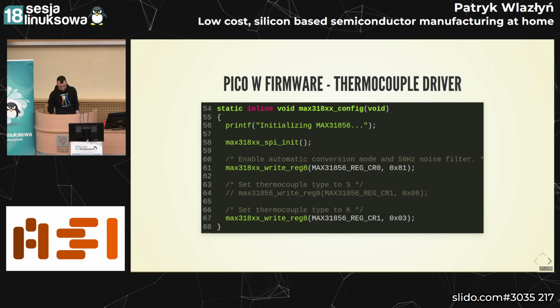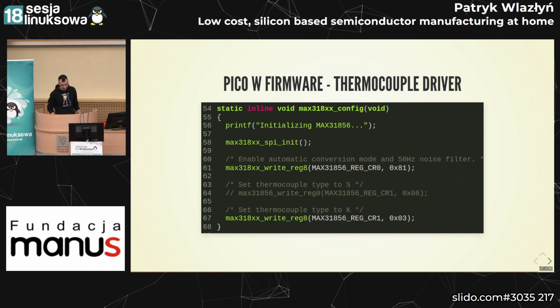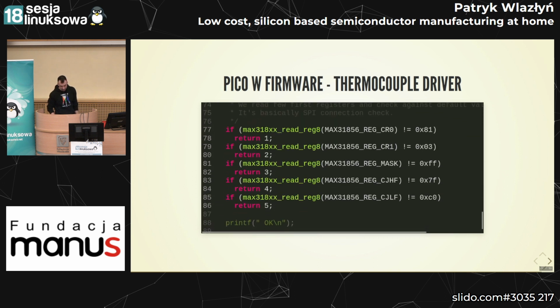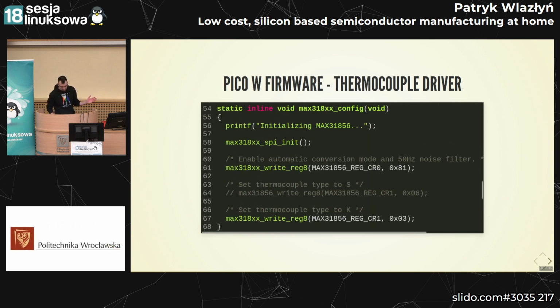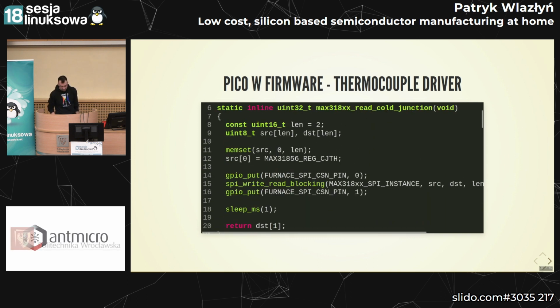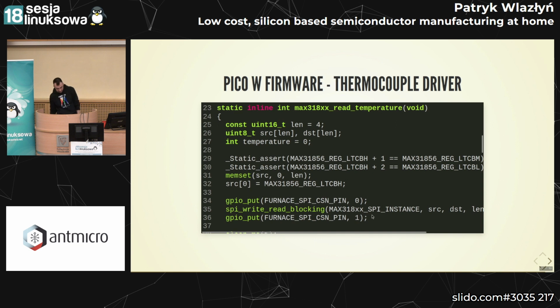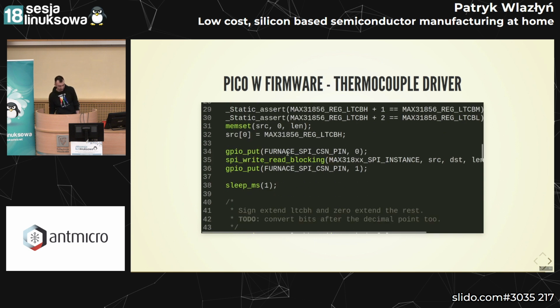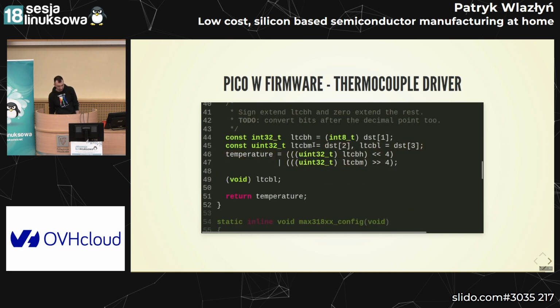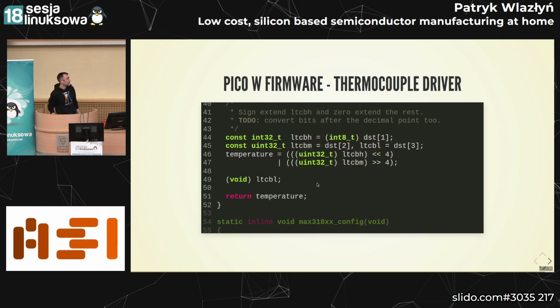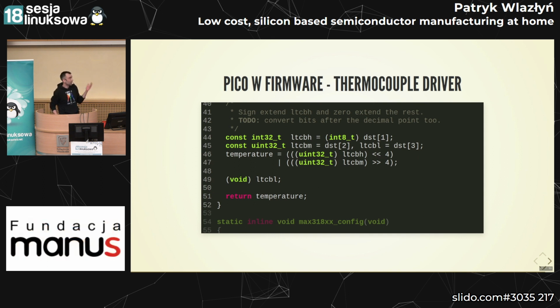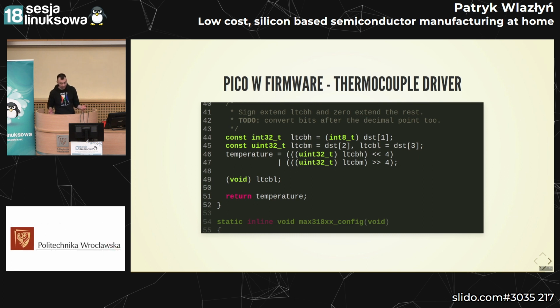There's a simple SPI interface for the thermocouple driver we're using. The main point is that for initialization, you just do two writes over SPI, and later reading the temperature comes down to one SPI transmission, shifting values from two registers to form a temperature reading. It's a very simple setup - you just take a driver and a thermocouple, and you can measure high temperatures between 0 and 1500 degrees C.